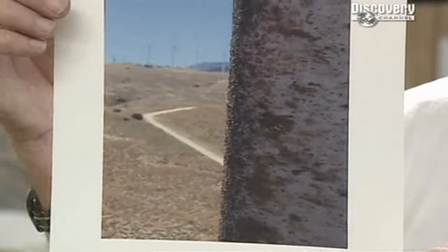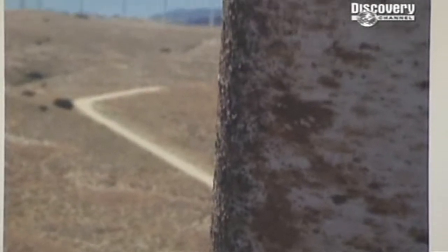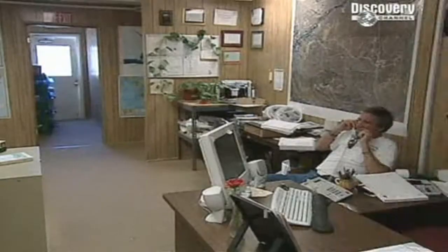The bugs deposit on the blade, on the leading edge, and when the air is supposed to follow the contour of the blade, instead of following it and staying attached, it's like it hits a speed bump, so it comes around and goes like this away from the blade, which causes it to lose lift, which is kilowatts. You could turn a 750 kilowatt turbine into a 400 kilowatt turbine just from bugs on the blades. Bugs can seriously hamper electricity production.